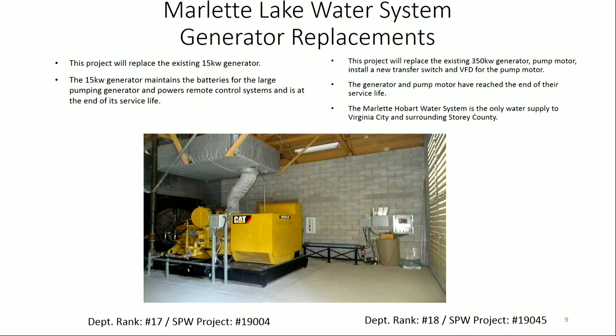Next, these two projects, numbers 17 and 18, are also related to the Marlette Lake water system. Project 17 would replace the small 15 kW generator, which besides being outdated and at the end of its useful life, supplies power to the remote control systems and maintains the charge on the batteries that start the large generator. Project 18 would replace the large generator because it's also at the end of its useful life, and along with the generator, we would change out the pump motor and install a new transfer switch and a VFD to operate the pump.